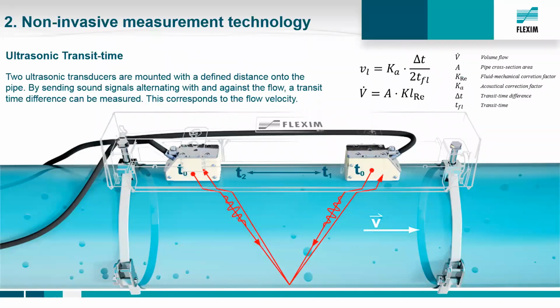So let us have a look at the measurement principle. How we measure is based on the transit time difference principle. Here you can see a picture of a pipe where two transducers are mounted. An ultrasonic clamp-on flow meter usually consists of a transmitter, which we cannot see here on the slide, and at least one pair of transducers and mounting assemblies. The transducers shown here at the top of the pipe are coupled onto the pipe. Ultrasonic signals are sent through the pipe and media from one transducer, reflected by the pipe wall here at the bottom and caught by the opposite transducer, which is acting as a receiver, and vice versa.